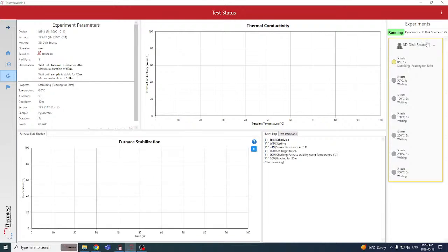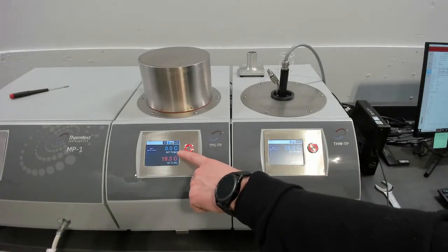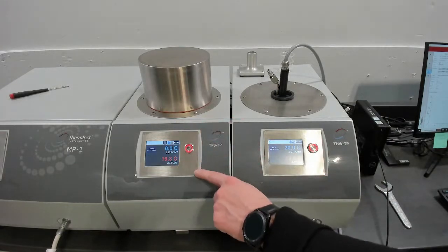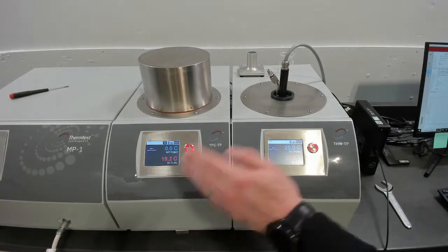we can confirm there's isothermal conditions inside the chamber at the sample level. So by clicking start on this particular channel, which is port number 2, I believe, a schedule is set up for running Pyroceram inside the temperature platform. You'll see the temperature change set to 0 degrees. If I change the camera and go back, you would see that.